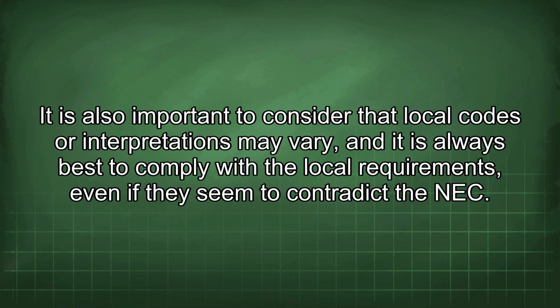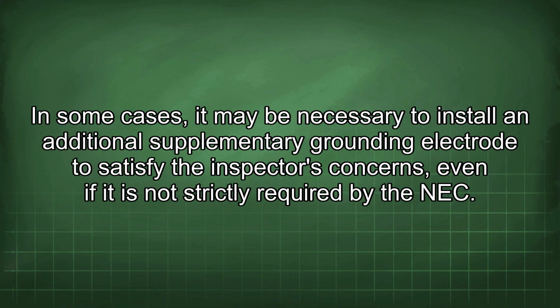It is also important to consider that local codes or interpretations may vary, and it is always best to comply with the local requirements, even if they seem to contradict the NEC. In some cases, it may be necessary to install an additional supplementary grounding electrode to satisfy the inspector's concerns, even if it is not strictly required by the NEC.